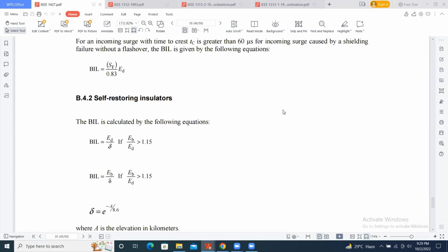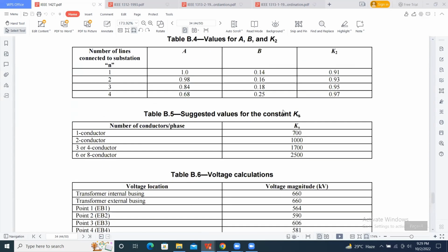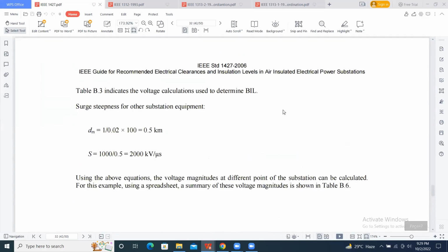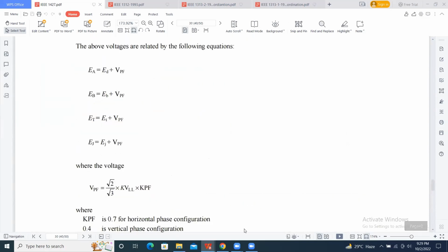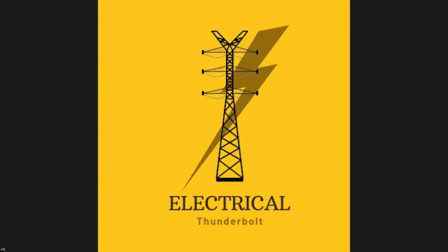So generally, no one is doing the insulation coordination study for now, and they are depending on some other tools. In ETAP also, I don't know. We are having this insulation coordination study. They are doing it in substations with high voltage levels like 400 kV or above 220 kV, then I would prefer to do this insulation coordination study, because of your 400 kV lines. Also, if the lines going out from your substations are traveling some far kilometers, then it's required to do this insulation coordination study, because you have to check the effect of the back flashover rate or CFO of the line.